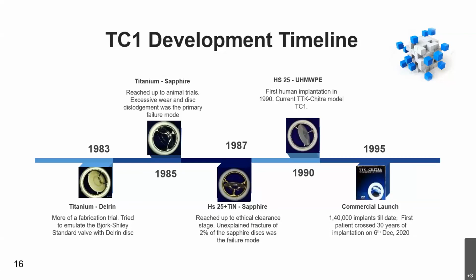Normally in engineering, we design any reciprocating or rotating machinery for about 10 raised to 6 or 10 raised to 7 or at the most 10 raised to 8 cycles. 10 raised to 8 cycles means about 100 million cycles. But here we have to have a design which works for 2000 million cycles. And that is the challenge in this particular device. None of the engineering reliability analysis like the S-N curves or the fatigue failure analysis or the shear energy strategies works for such a long duration fatigue environment. And that is where a lot of evaluation and test systems had to be fabricated and validated to ensure that the device will work for a period of 2000 million cycles.